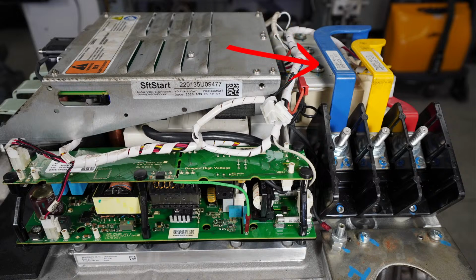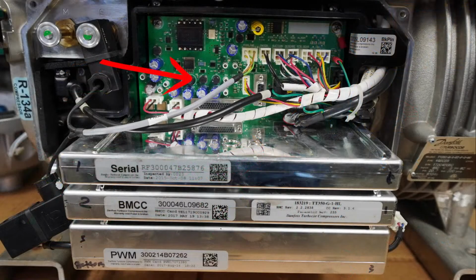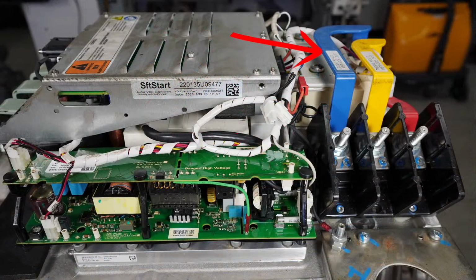More than likely, though, when I've had a situation like this, it's actually not an SCR issue. When I have power into the compressor, but I don't have anything on the backplane, typically that is not an SCR issue in my experience. It's usually something to do with the DC to DC converter itself.